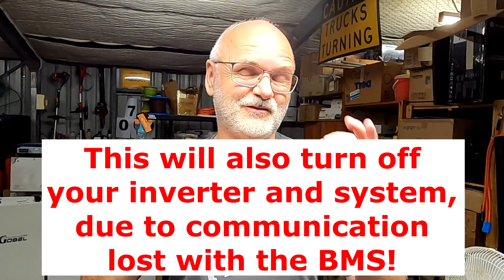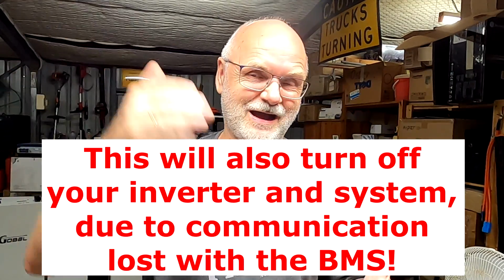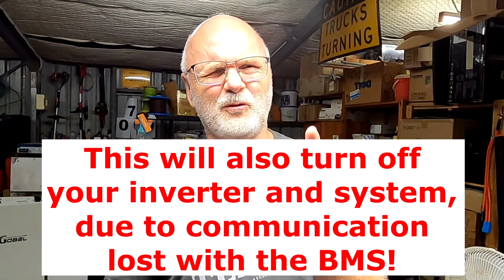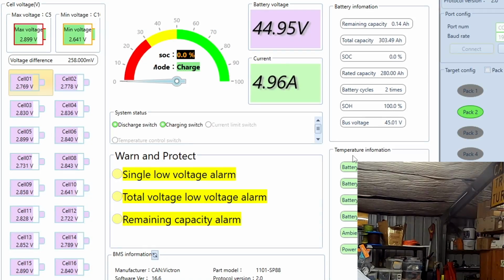So if you have a single cell or pack undervoltage protection, the Seplos BMS obviously turns completely off, doesn't talk to the master battery or to your inverter anymore, and it is only waiting for charge to come in. I think we have seen this before with the Pace BMS. Was it the Pace BMS? I can't remember, but one of them also completely turned off when we hit the low voltage disconnect.